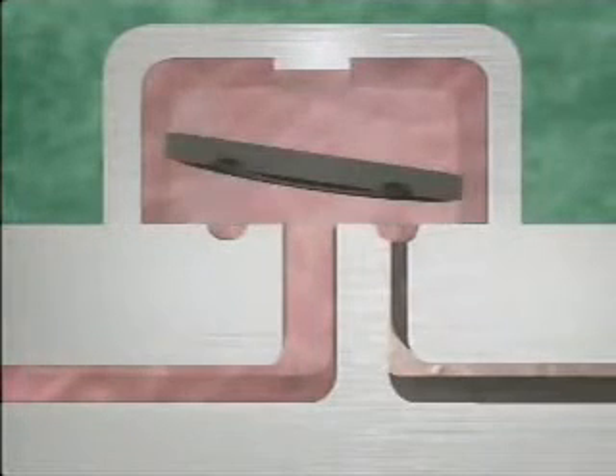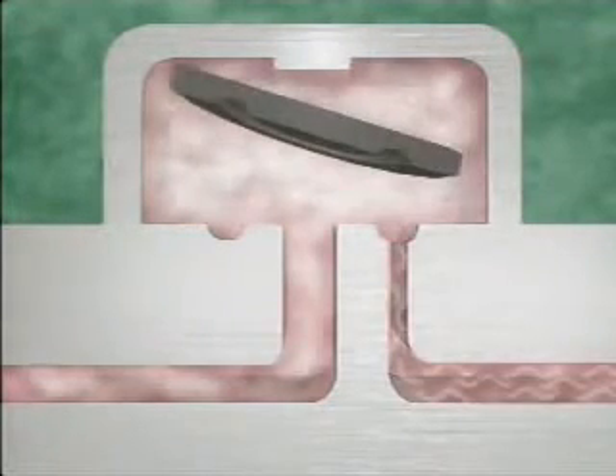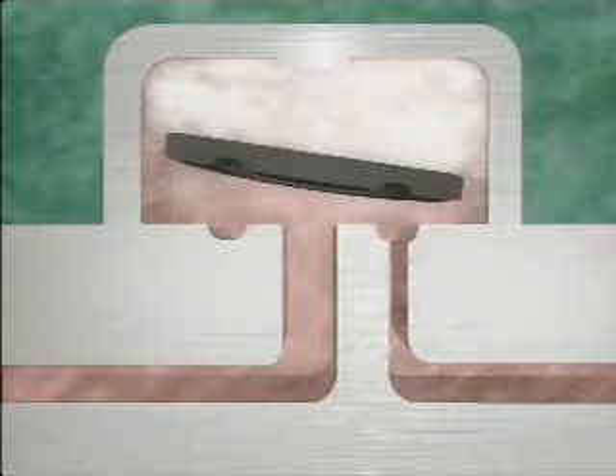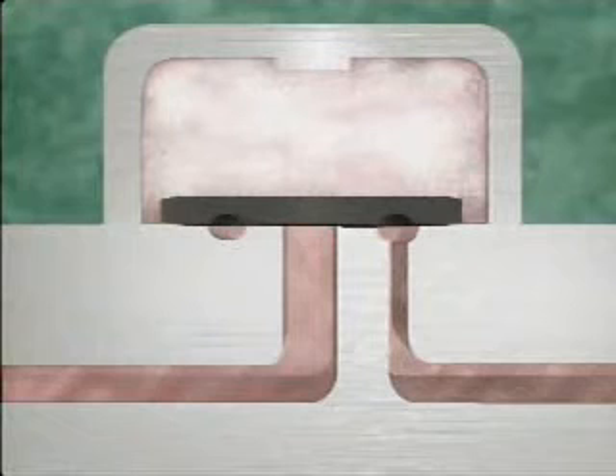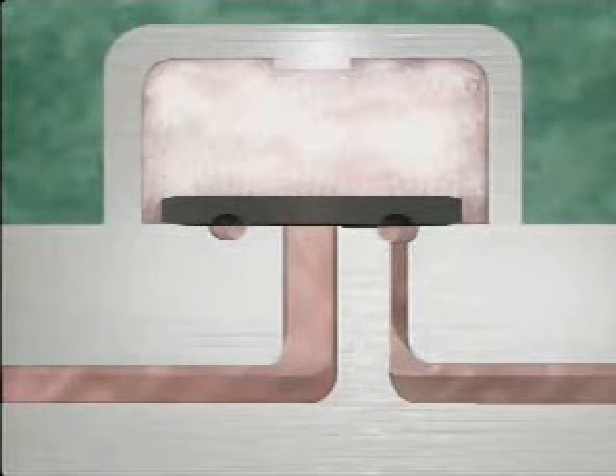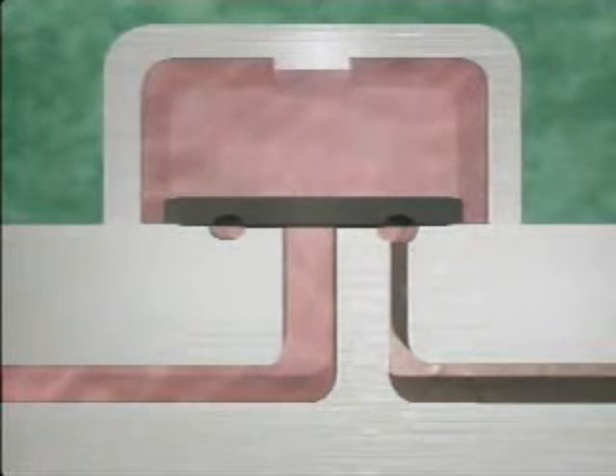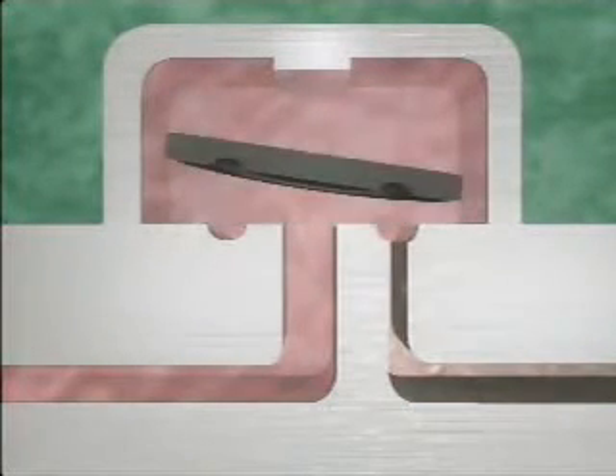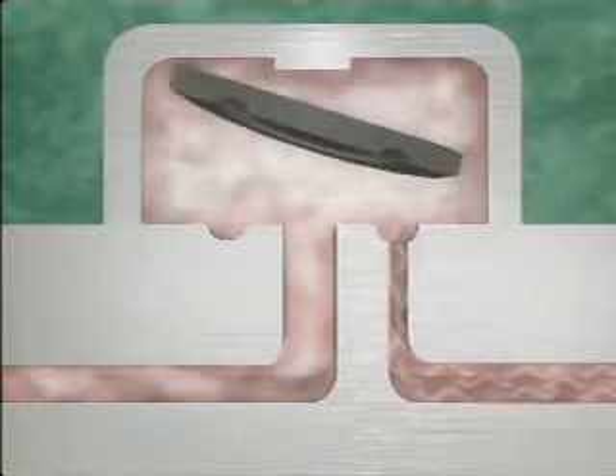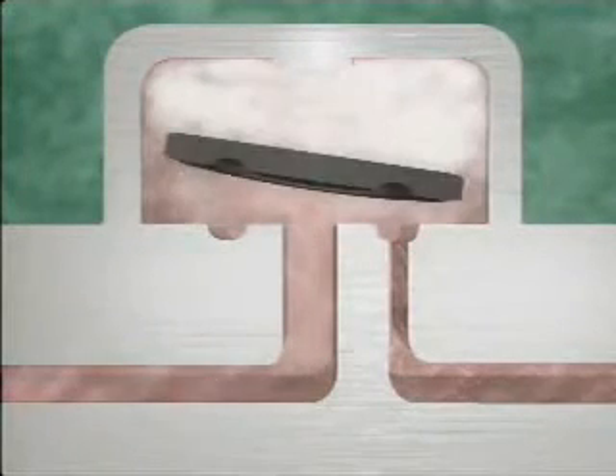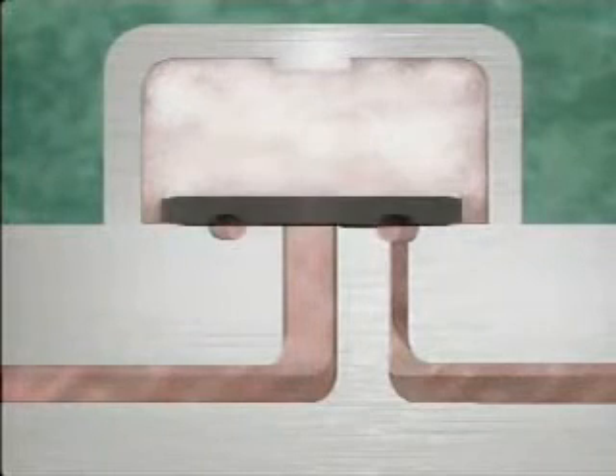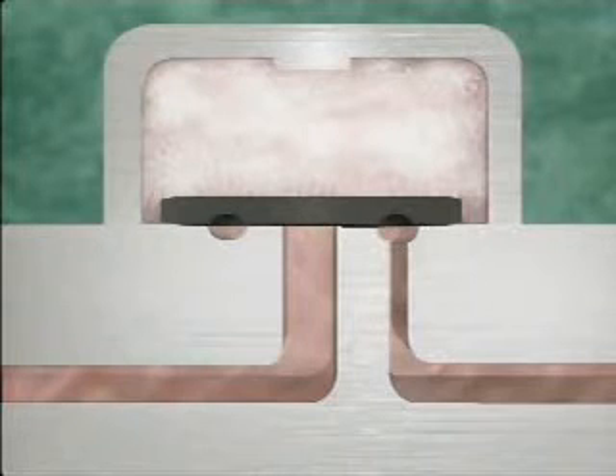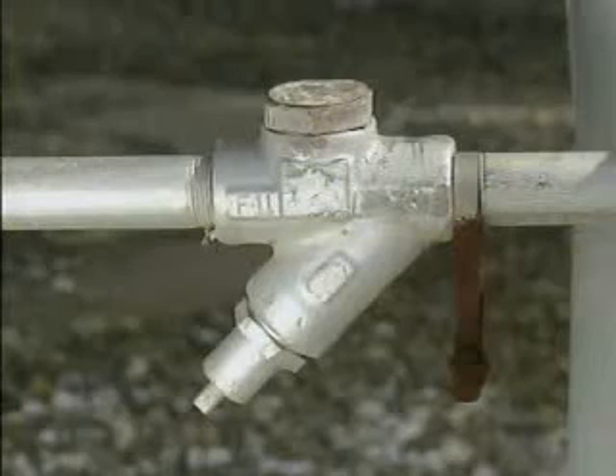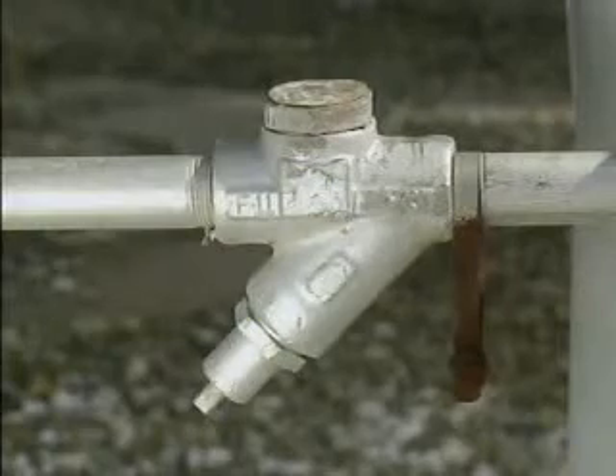Because it operates on a time cycle, as long as the temperature and pressure at the trap inlet remain constant, a disc trap stays closed for the same amount of time, typically 5 to 10 seconds, each time that it closes. Condensate that comes to the trap in the middle of a time cycle won't be discharged until the pressure above the disc falls low enough to allow the disc to rise and reopen the trap. Since the movement of the disc cycles between the open and the shut positions, the discharge from the trap is intermittent.